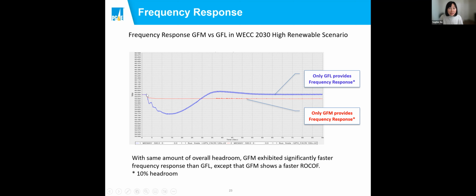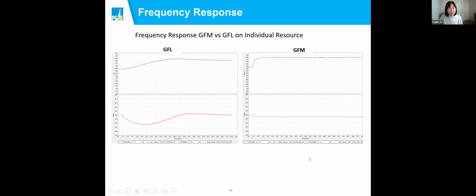The only thing that I can see a little bit not as good as grid following is the ROCOF, which tends to be a little higher, faster than grid following, but it rescued the frequency much sooner. So I would think it still outperforms the grid following inverter. And these are just basically the performance of individual grid following versus grid forming in a frequency event.